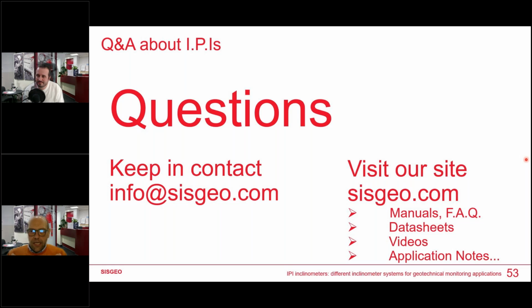We calibrate our sensors and we give the MPE, the maximum permitted error, as in the datasheet. The maximum permitted error that we calculate in the calibration is across the entire full range of the sensor. Actually, the maximum error is not in the vertical position, but near the full scale position. So the ISO standard is just requesting to keep the probe as vertical as possible, in order to use it in the most accurate position possible. I hope this is clear enough.